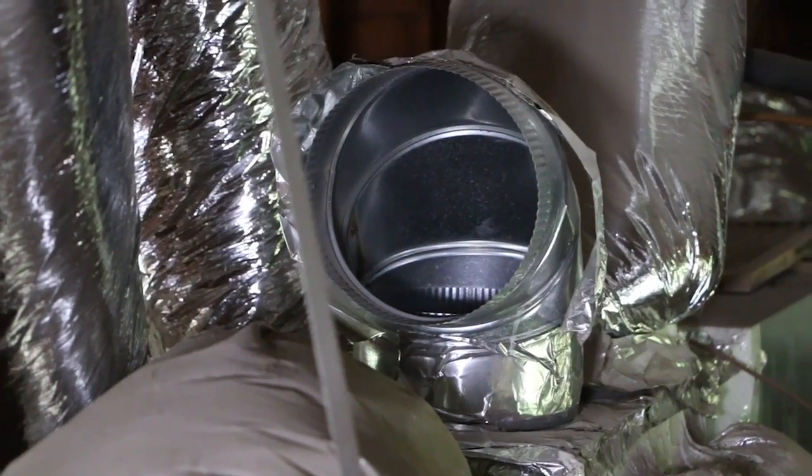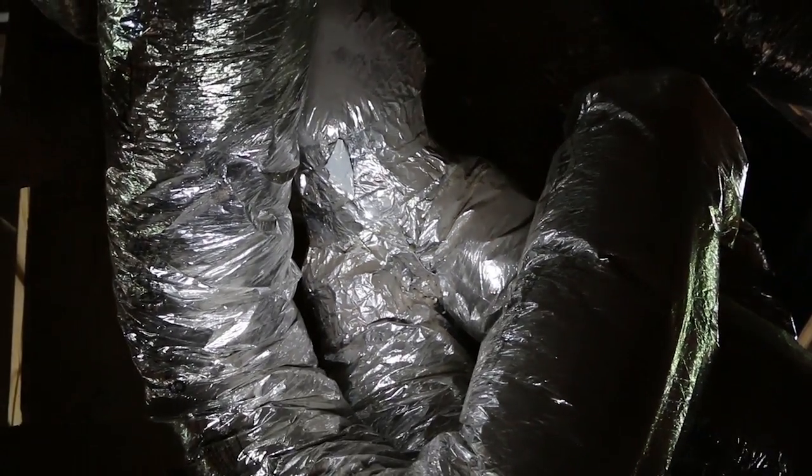Some of the leakage pathways were pretty easily identified, such as a supply duct that was just laying disconnected from the actual air handler. Other leaks were a little more hidden, and it took us a second to find.